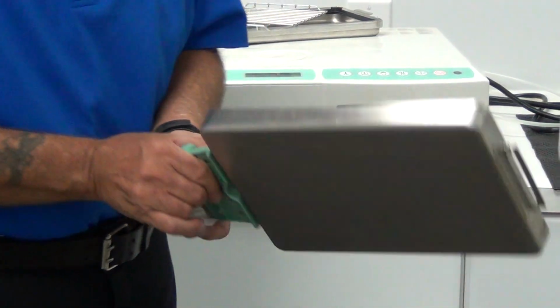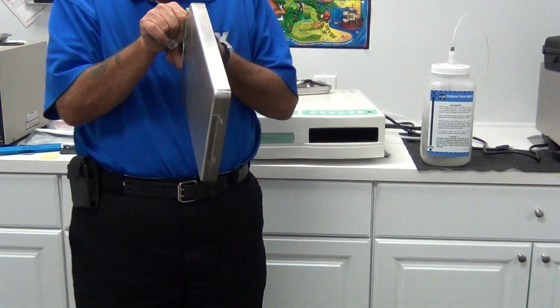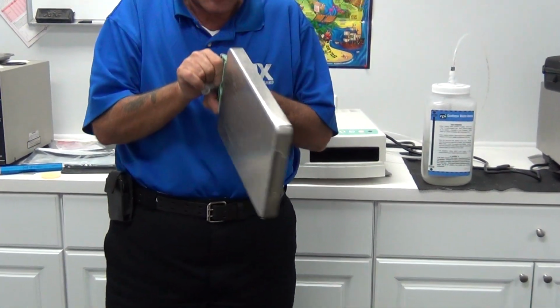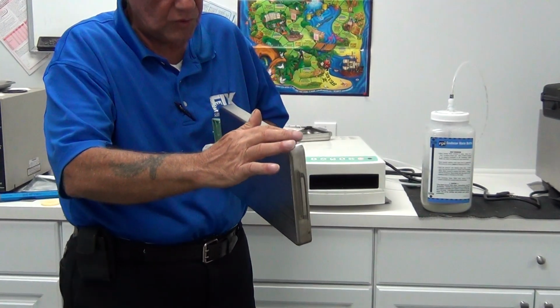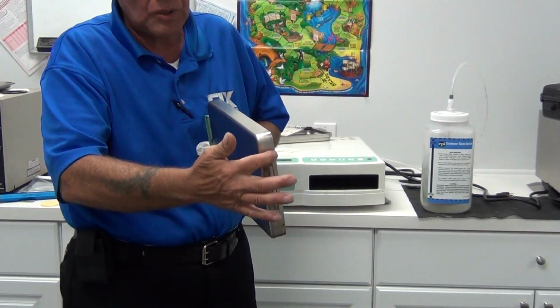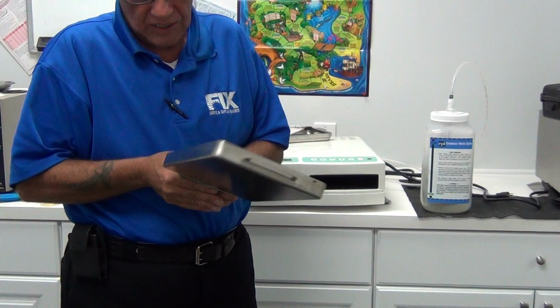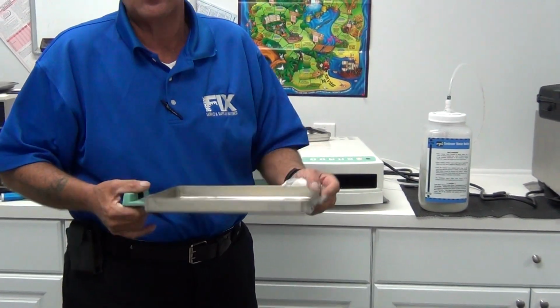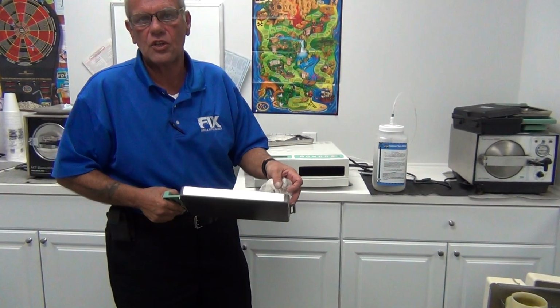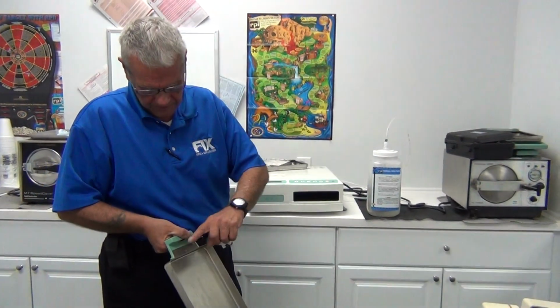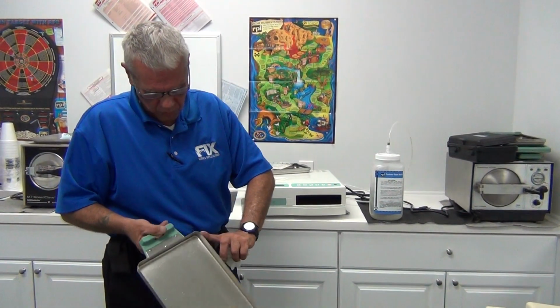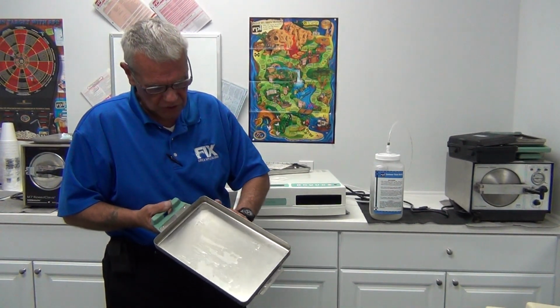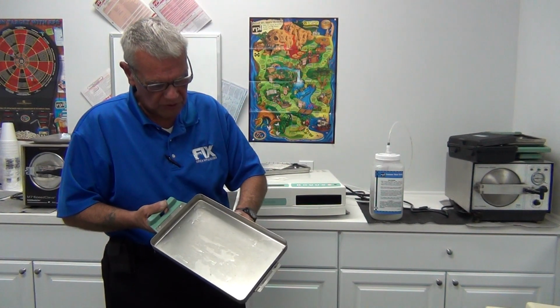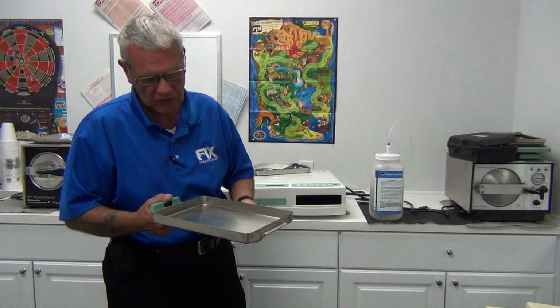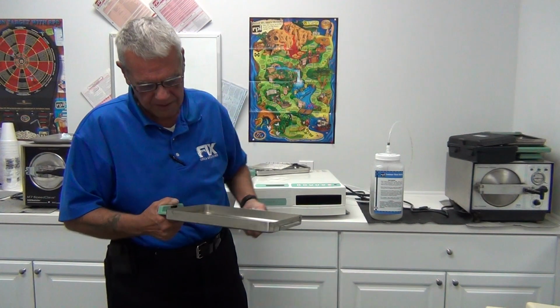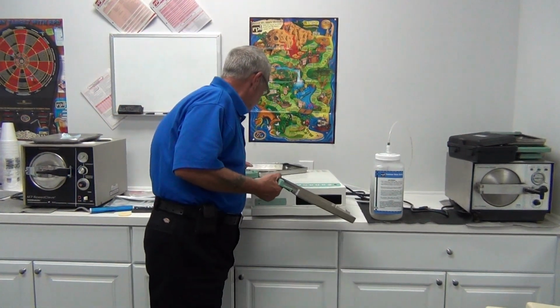Now we're going to examine the bottom of the cassette just like this. We'll look straight down it on the edges to make sure that we don't have things built up on the edge. Any pieces of debris or soap where somebody went crazy using the soap to lubricate the gasket. We're going to run our finger across it and make sure we have a smooth periphery with no dents or debris so we get a good seal. Okay, now we can lay the cassette aside.